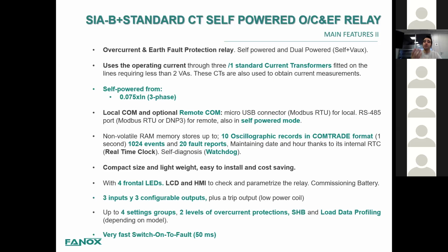Also, as with all of our self-power relays, we have local communication through a micro USB connector and remote communication with Modbus RTU or DNP3, which is also available in self-power mode. Regarding storage of the events, we have 10 oscillographic records in COMTRADE format, 1,024 events, and 20 fault reports. And of course, we maintain the time and date thanks to the RTC. Also, you can configure a watchdog output or alert to have this indication on your installation. It has a very compact size and is easy to install, lightweight, and cost saving.